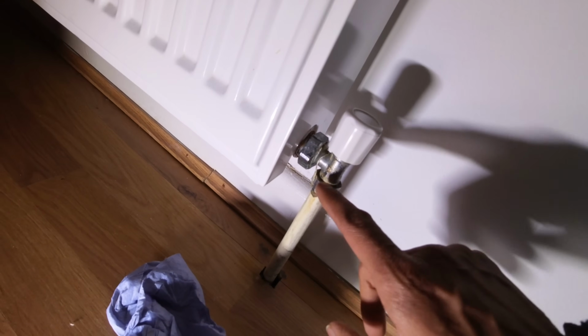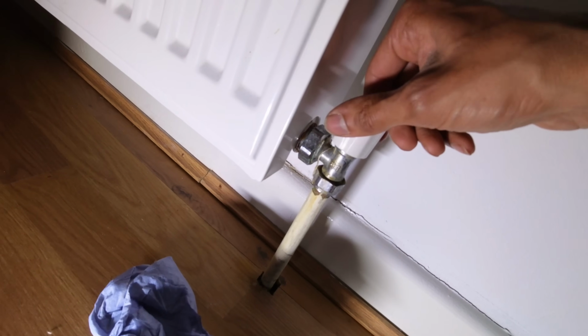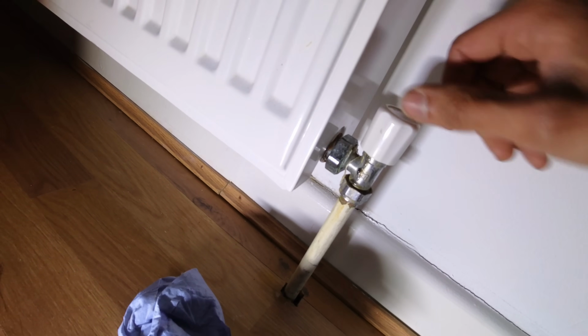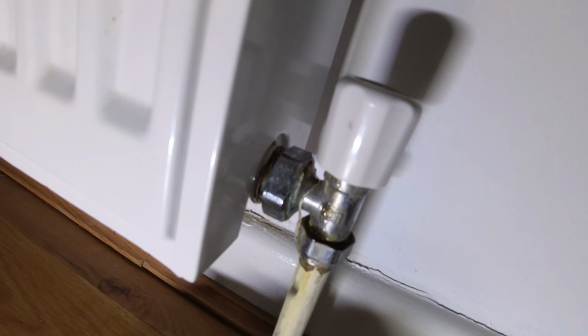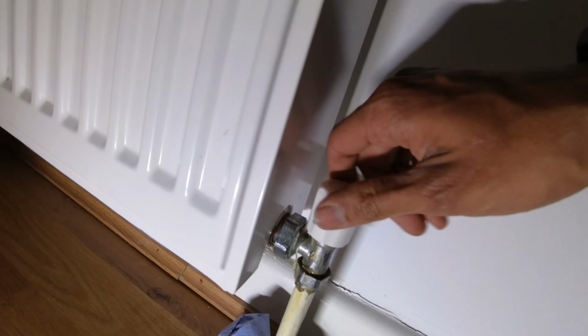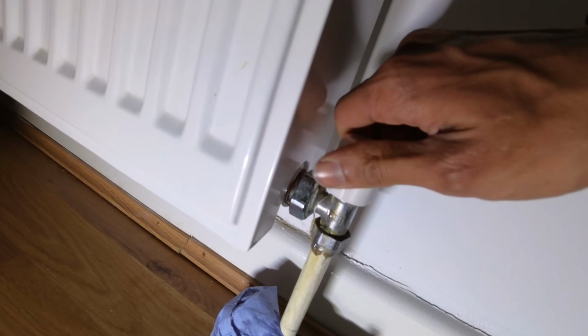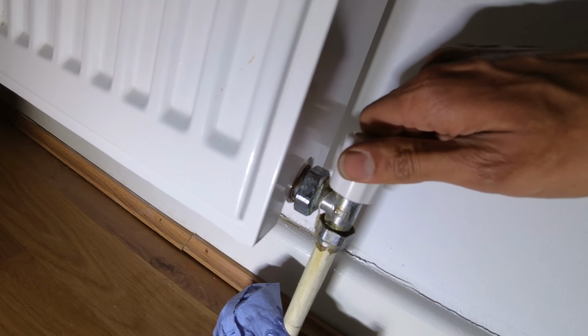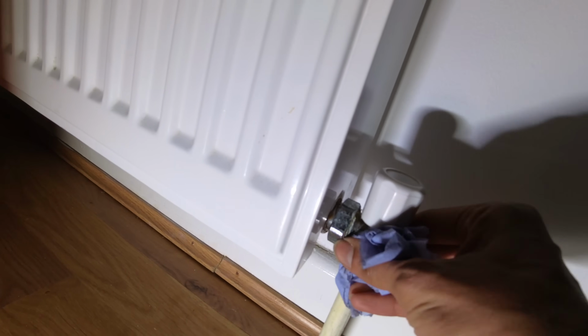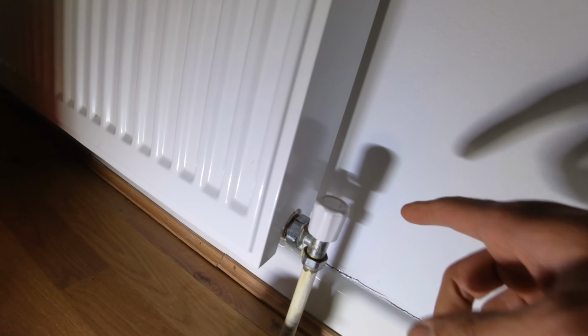Right, last job here. We've got a leak from a rad valve. So when I open this lock shield up, you can see it starts to drip there. So that's fine, at least we know where it's leaking from. I'm going to whip this off, dump the pressure out, and then just swap the valve over.